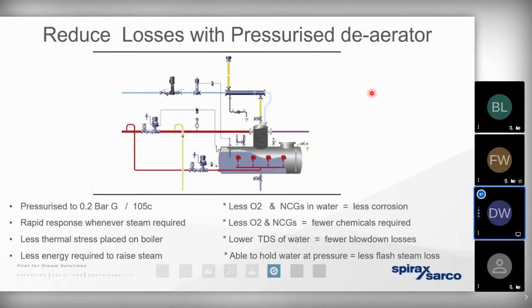So first of all, higher temperature water, well, it means the boiler is going to respond more rapidly. It means we get less thermal stress placed on the boiler. And of course, it means we need to consume far, far less fuel to generate steam if we're bringing water into the boiler at 105 as opposed to 85 degrees. Other benefits, at that high pressure, it means that we've purged off that oxygen and the non-condensable gases mechanically. We don't need to add anywhere near as many water conditioning chemicals. So if we've got less oxygen, fewer gases present within the steam, we get less corrosion of the pipework. We get a better condition of steam being produced. We need to perform far, far less blowdown because there's going to be a lower TDS level within the water. Less blowdown, that means fewer energy losses.